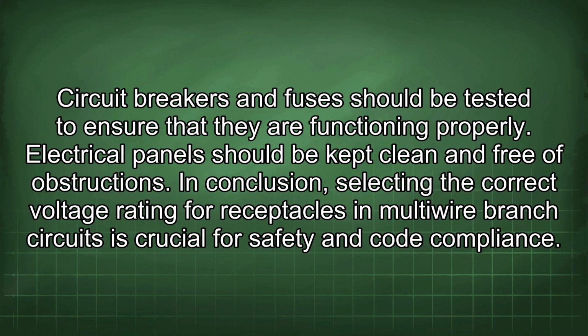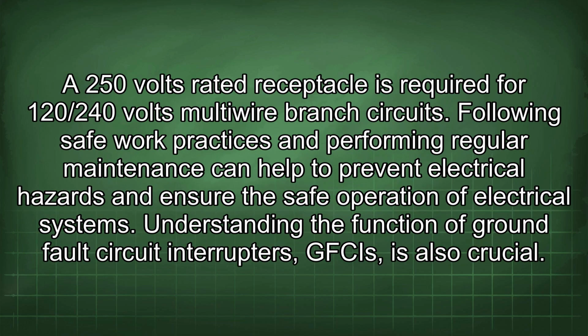Circuit breakers and fuses should be tested to ensure that they are functioning properly. Electrical panels should be kept clean and free of obstructions. In conclusion, selecting the correct voltage rating for receptacles in multiwire branch circuits is crucial for safety and code compliance. A 250 volts rated receptacle is required for 120/240 volts multiwire branch circuits.